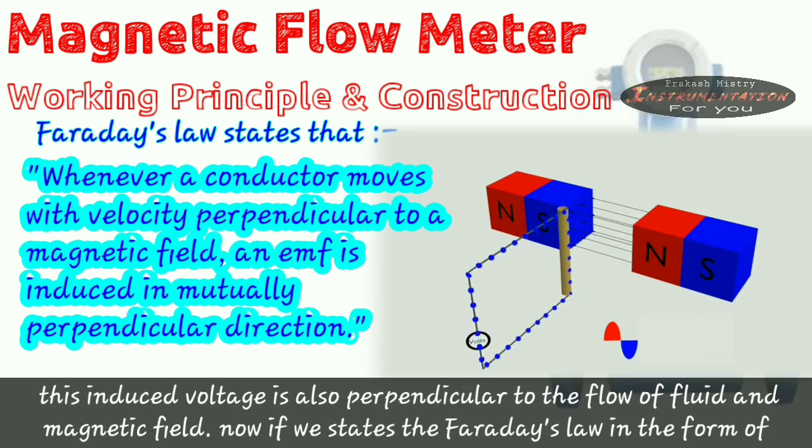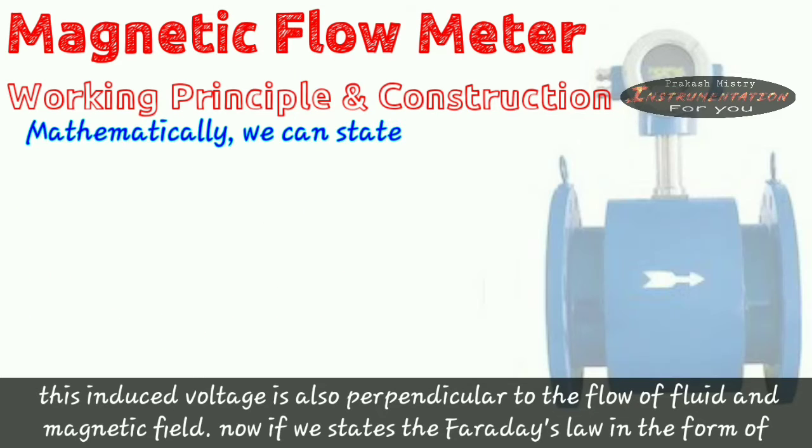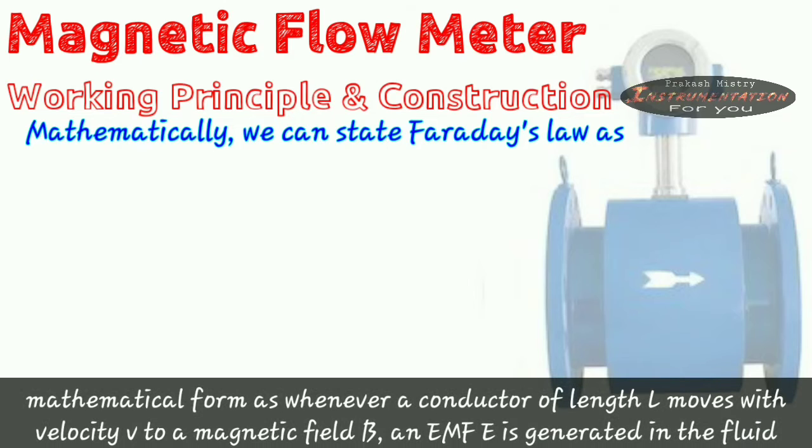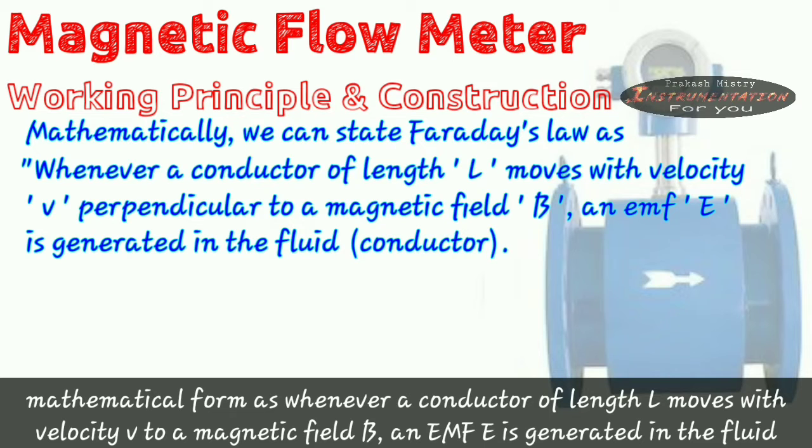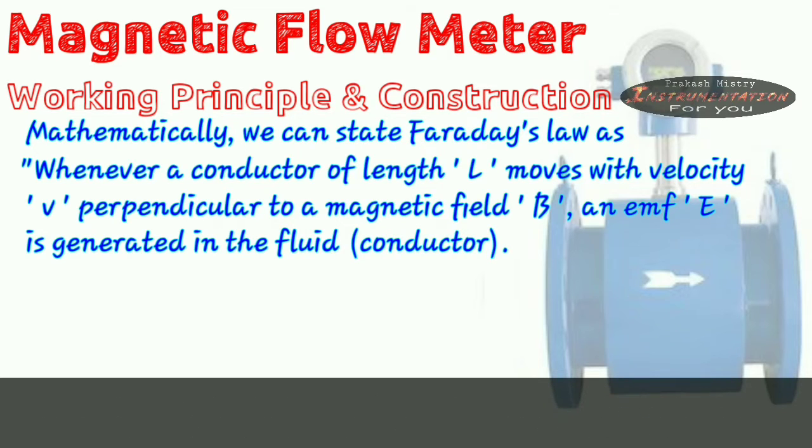And this induced voltage is also perpendicular to the flow of fluids and magnetic field. Now if we state Faraday's law in the form of mathematical form, whenever a conductor of length L moves with the velocity V to a magnetic field B, an EMF E is generated in the fluid.